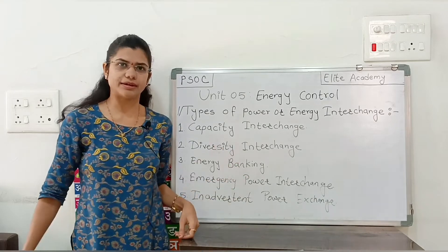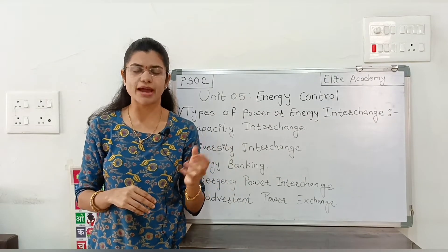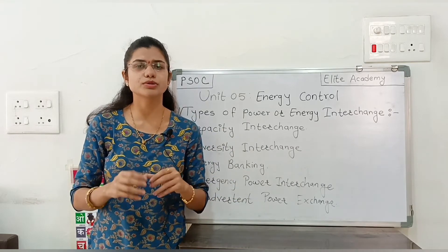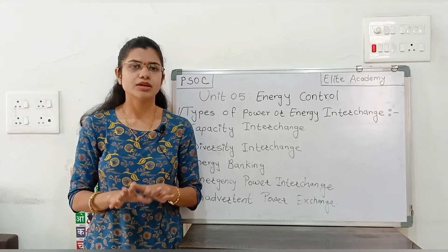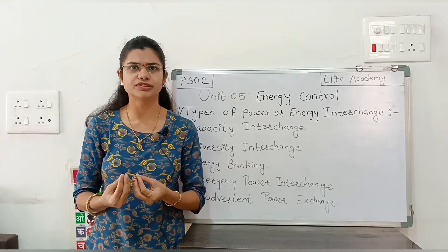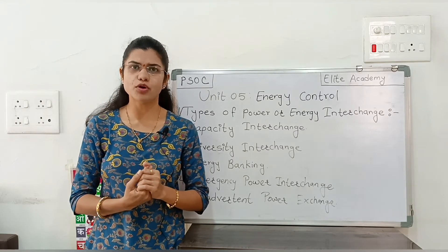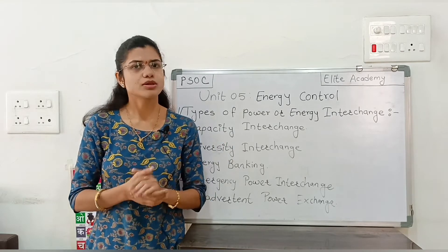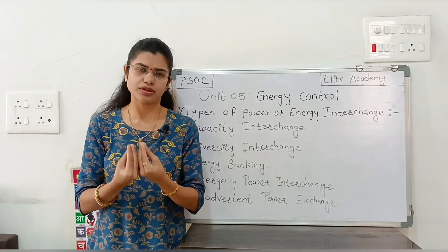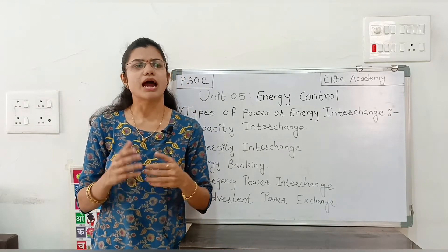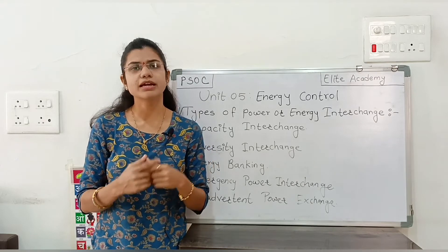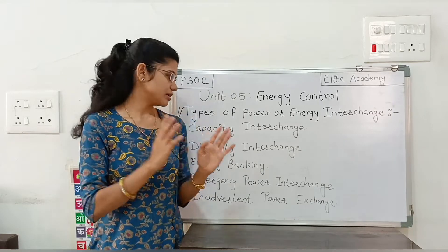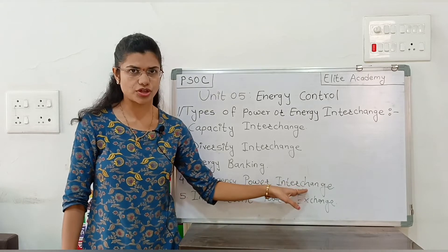The third type is energy banking. The name itself indicates one party is the banker and one is the depositor, but it totally depends on who is buying and who is selling. For example, consider a hydro system and a thermal system. During a high water runoff period, the hydro plant generates more energy and sells it to the thermal plant. During a low water runoff period, the hydro plant buys energy from the thermal plant.